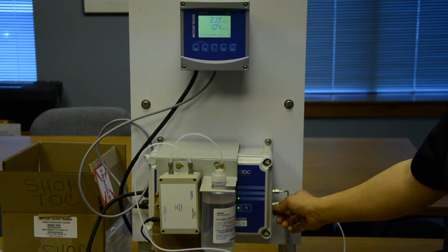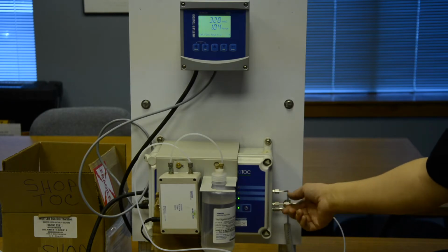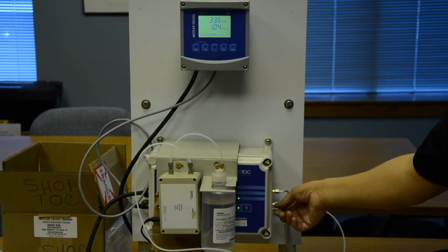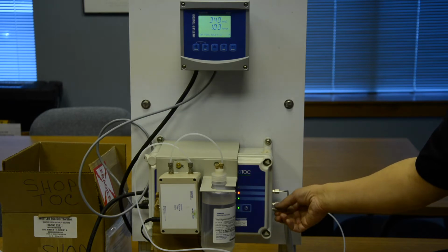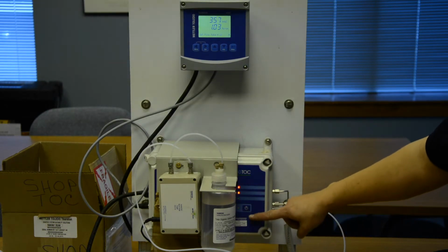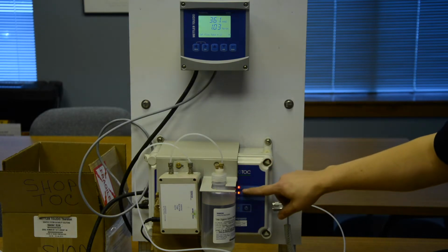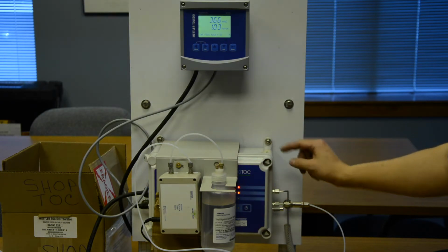When you have a low flow, your lights will go down toward the bottom and the top lights will disappear, signaling that you have low flow on your unit. Turn your needle valve to the left, counterclockwise, to open your valve to increase the flow. If your flow is too high, your lights will start disappearing from the bottom and go up to the top, signaling that you have high flow.